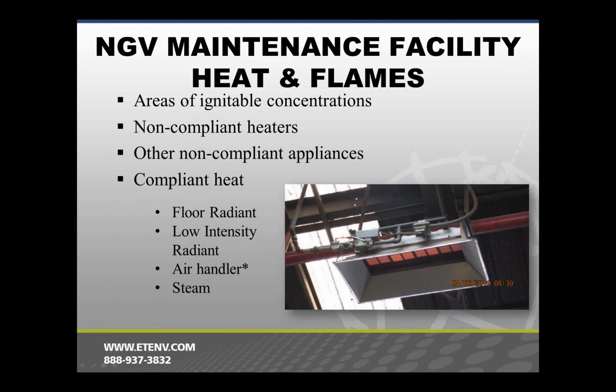The heat, I talked about the basic requirements of the heat, 750 degrees and no open flames. What you see in the picture here is a non-compliant heater. In fact, it's a radiant heater that's a sort of high-intensity model. It exceeds the 750-degree limits. We can tell just by the red color there. And most heaters that you'll find in shops, unfortunately, are non-compliant.